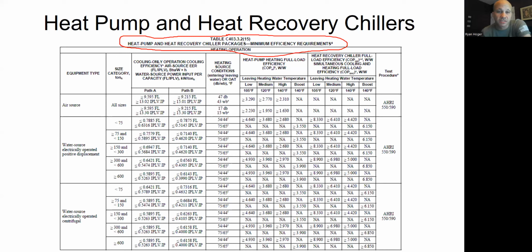We did that in this case. This is the heating efficiency table. So you do that, and then you've got to figure out what kind you have. Air source, meaning the heat pump is going to be taking its energy from the air and giving it to the air, specifically in the heating mode, taking it from the air.